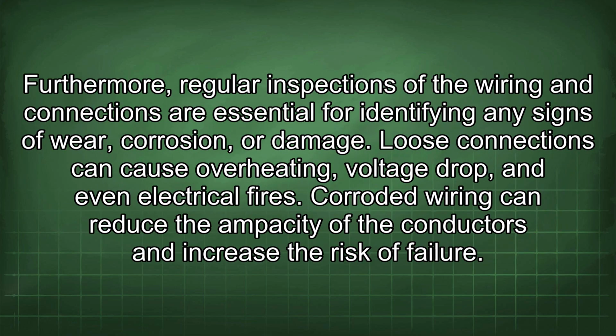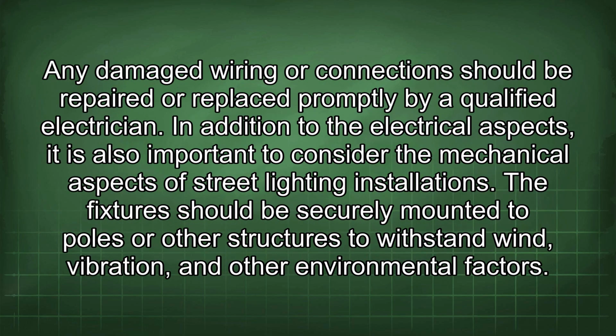Furthermore, regular inspections of the wiring and connections are essential for identifying any signs of wear, corrosion, or damage. Loose connections can cause overheating, voltage drop, and even electrical fires. Corroded wiring can reduce the ampacity of the conductors and increase the risk of failure. Any damaged wiring or connection should be repaired or replaced promptly by a qualified electrician.